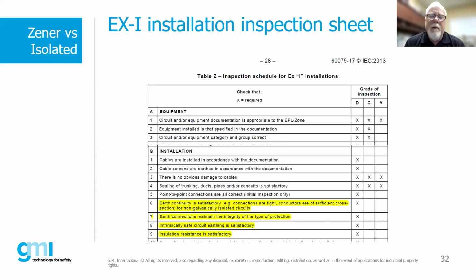Now, talking about intrinsic safety a little bit from an inspection standpoint. This chart is from the 60079-17. This is actually an older version, but it hasn't changed from the latest version of the -17 with regards to intrinsic safety. But when we do an inspection of intrinsic safe installations, these are some of the key things that we really want to check.